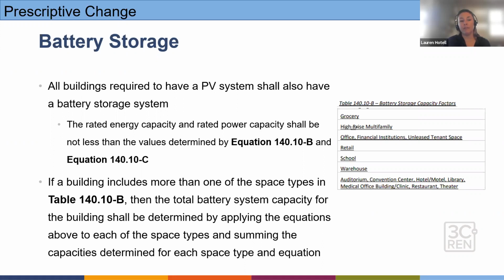And then if the building has more than one space type, then the battery system capacity for the building needs to be determined by both equations. So you do equations for both use types, sum them together, and that's how you get your system size.